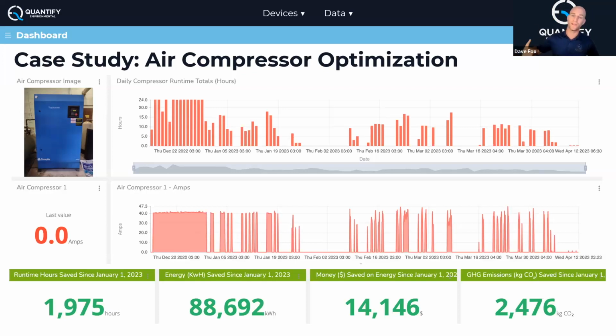The next step we did - and this is where Quantify has those 2 different stages of our projects: visualizing the data, but then actually acting on it and working with clients to implement it - we went out in the field and started talking to the guys on the production floor. What PSI do you need to do your job? The end result was about 90 to 100. We went back - this machine was chasing constantly 124 PSI. So we slowly dialed it back 2 or 3 PSI every week. Now not only is it using a lot less energy when it shouldn't be running, it's using less energy when it needs to be running.